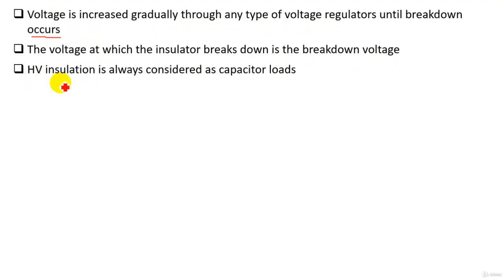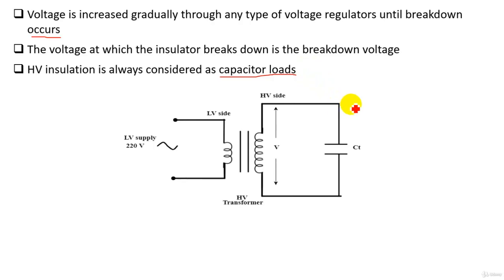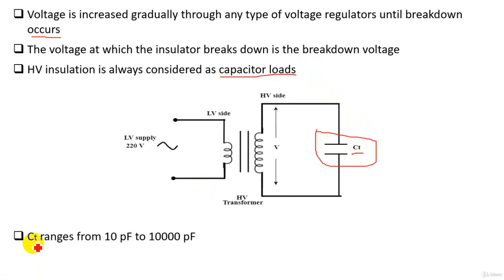We know also that high voltage insulator is always considered as a capacitor load. Why insulator is considered as a capacitor? Because it is a dielectric and it's also placed between two electrodes or two conductors, high voltage electrode and the earth electrode. So this is a representation of the capacitor. So we can represent the insulator here by a capacitor, and it's called Ct. While Ct is the capacitor of the insulator, and it ranges from 10 picofarad to 10,000 picofarad.